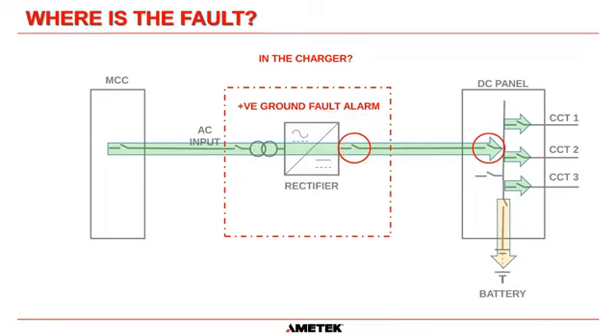Unless maintenance has been performed on that charger, and somebody has replaced the DC capacitors inside this system. So there's a positive and negative. What I've seen is that DC capacitors are aluminum, so the casing of the capacitor is conductive, but it is covered in an insulated material. You'll find a clamp that looks like this, where a screw goes through here, and there's a mounting bracket there, there, and there. You're supposed to fit the capacitor into this bracket and then tighten this screw to clamp it down.